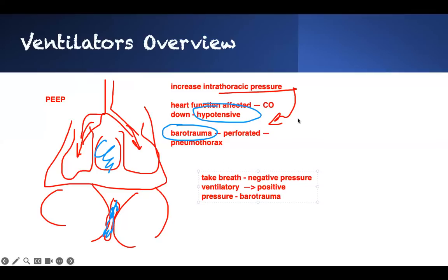Guess what? The ventilator can make noise when the pressure in the system is too high or too low. And that's the alarm that you have to know, the pressure alarm. There are two types: low pressure alarm versus high pressure alarm. Sometimes they use volume. It's the same thing. So it's a low volume alarm, but low volume creates a low pressure, and high volume creates a high pressure. They're just related. This will create the low pressure. This will create a high pressure.